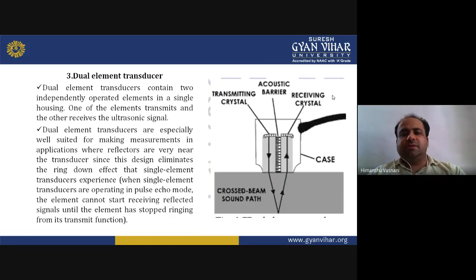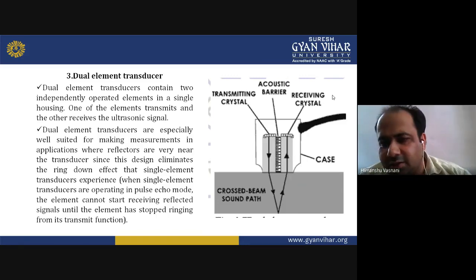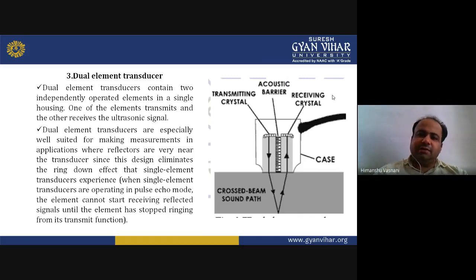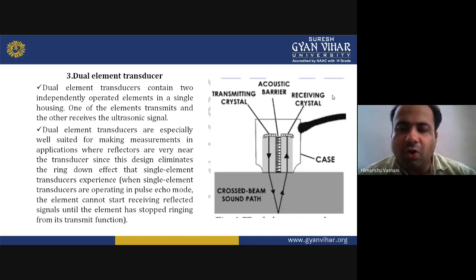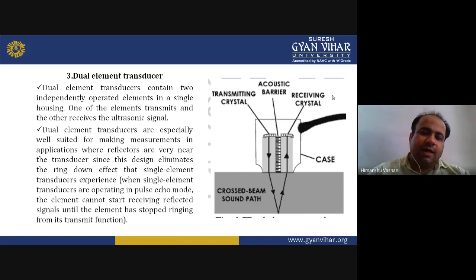Now, the dual element transducer. This transducer is very important. As the name says, it contains two elements in a single housing. You can see in the diagram there is an acoustic barrier. Then there are two different things: one is the transmitting crystal, and the other is the receiving crystal. And this whole system is in a casing. On the bottom side you can see the crossed beam sound path. Two elements are operating: one may be transmitting and the other receiving the ultrasonic signal.